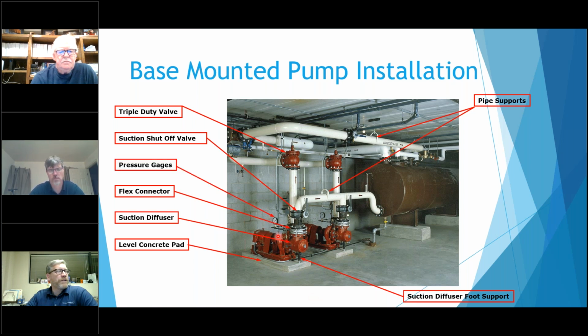And then they got pressure gauges in here. Generally speaking, I like to see just one gauge. That way you don't have to worry about the plus or minus error of the gauge. They would essentially have the same error. So it's nice to have just one gauge. I know sometimes you end up putting a couple in there. It still works, but it gives you a little bit better accuracy with just the one gauge in there. So it's very important to put one on.